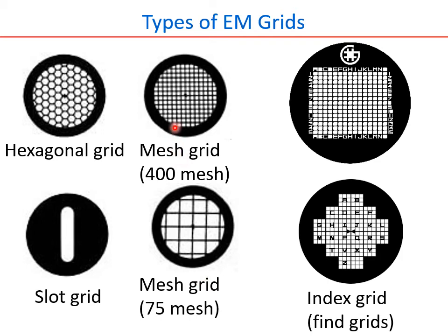You can see the 400 mesh is dense in nature, and naturally this can give better stability to the film as compared to the 75 mesh. So 75 mesh is going to have fewer square grids here, and this is going to give fewer anchoring points, thereby giving less support for the support film. So that means the 400 mesh can give better stability than the 75 grid. Does that mean that this is the universal choice?